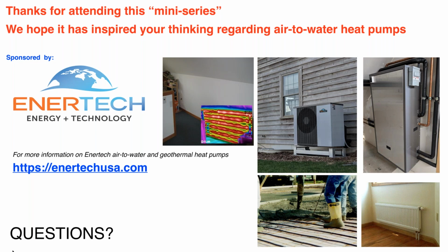No, copper is kind of a traditional hard piping material in hydronics, but certainly with the temperatures and the pressures involved, they could use PEX. Today, again, copper is being used. Actually, in the photograph over here on the far right, you can see copper tubing with what are called press fittings. These are becoming a lot more popular. And again, the pressure and temperature rating on press fittings well exceeds anything that these heat pumps will be operating at. It really comes down to the installer's choice.